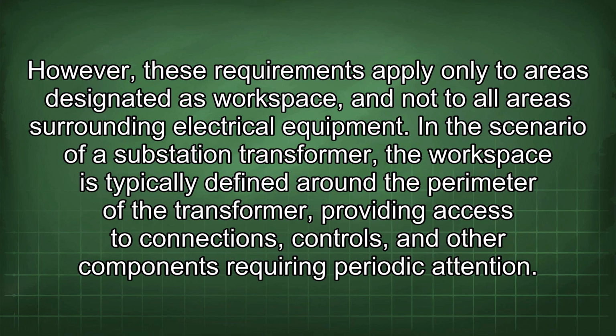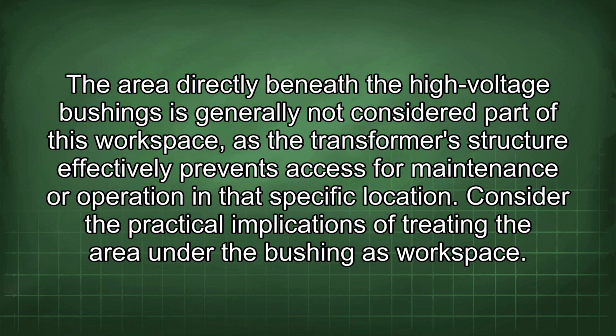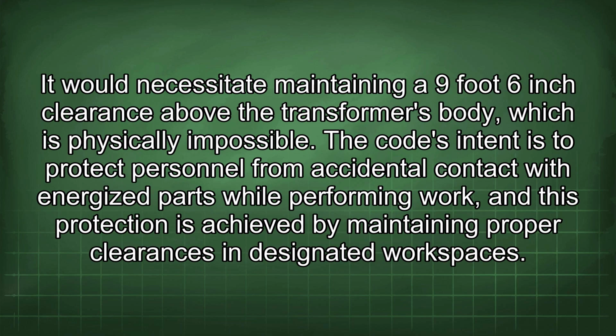In the scenario of a substation transformer, the workspace is typically defined around the perimeter of the transformer, providing access to connections, controls, and other components requiring periodic attention. The area directly beneath the high-voltage bushings is generally not considered part of this workspace, as the transformer structure effectively prevents access for maintenance or operation in that specific location. Consider the practical implications of treating the area under the bushing as workspace. It would necessitate maintaining a 9 foot 6 inch clearance above the transformer's body, which is physically impossible.